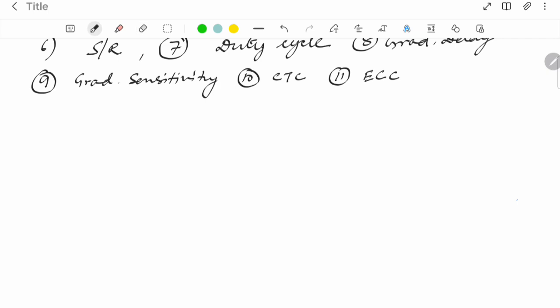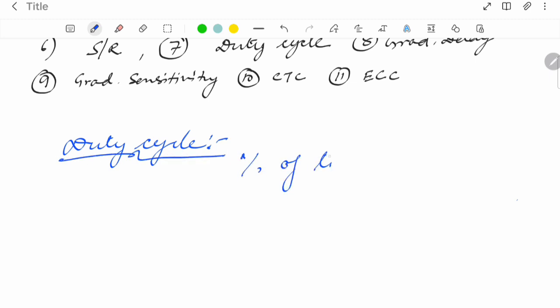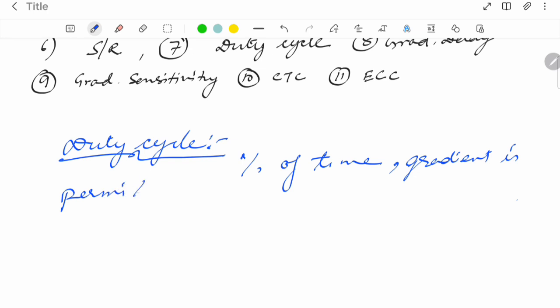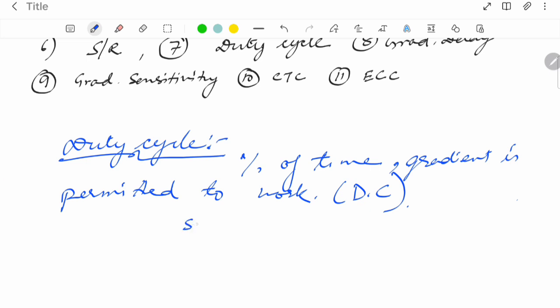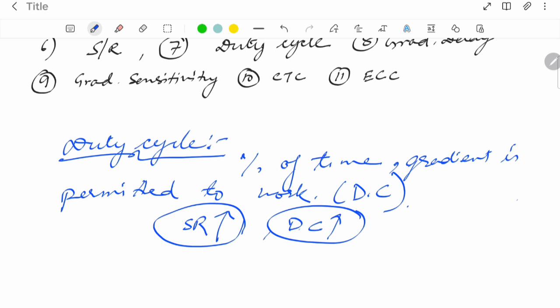The next common term is duty cycle — the percentage of time the gradient is permitted to work. If the slew rate is high, the duty cycle will be high, meaning the gradient is working more. A high duty cycle also means very high heat generation in the gradient, so you need to maintain a chiller system.